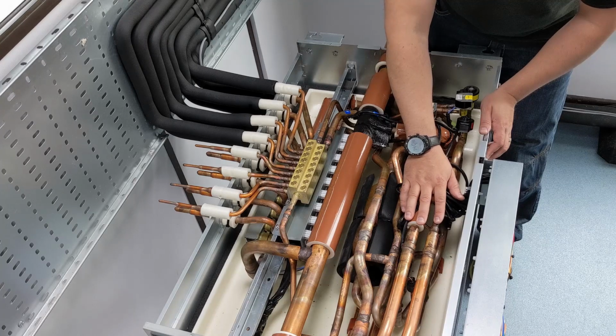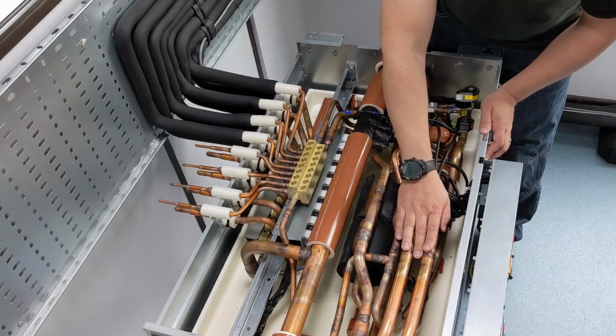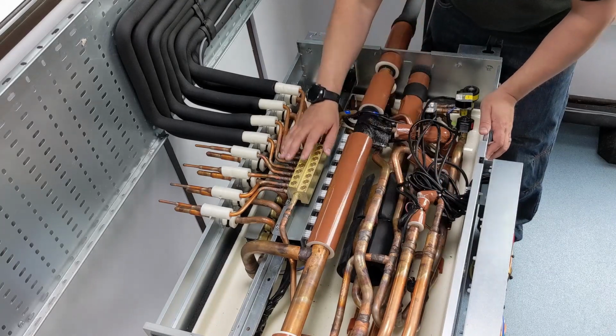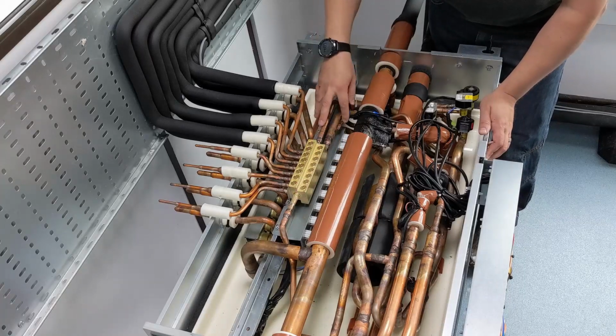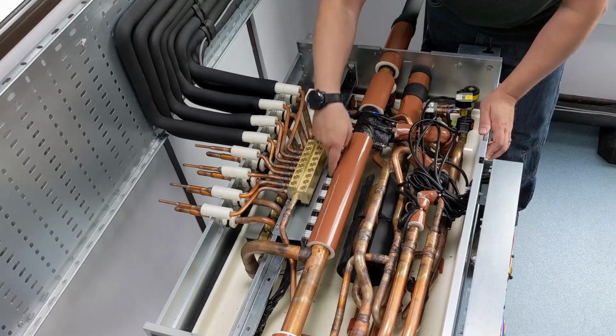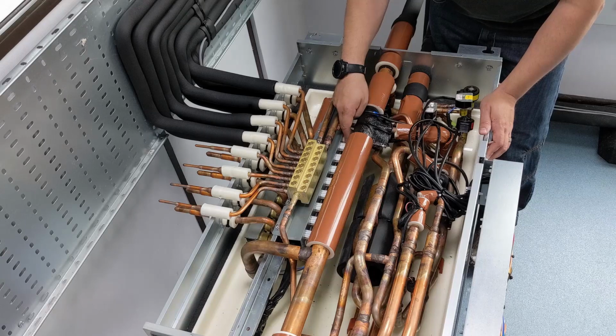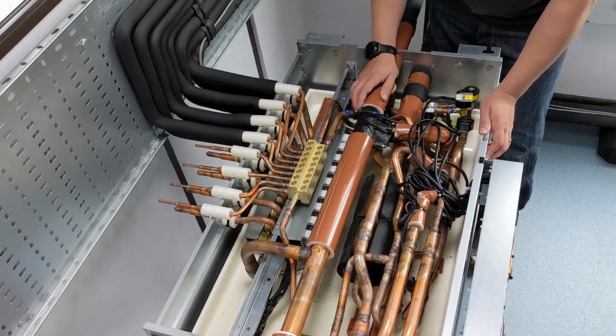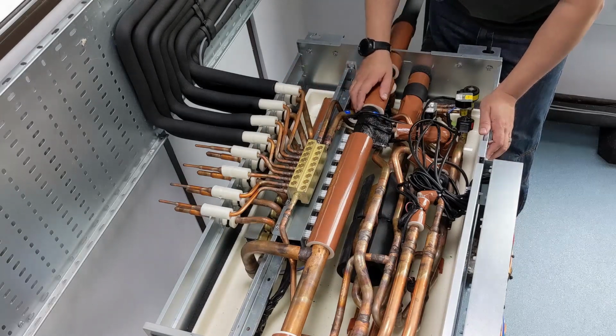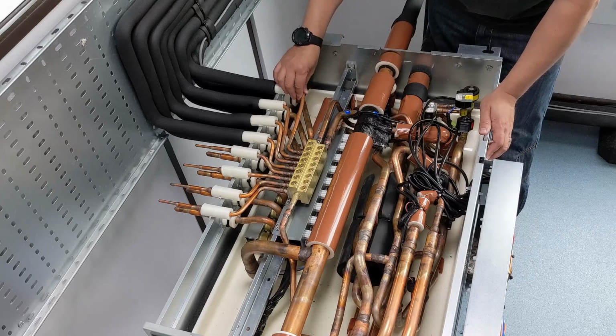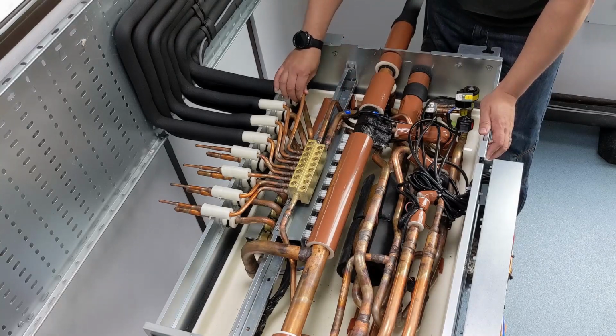We run the indoor units as flooded evaporators. That is until they're within 2 degrees of set point. So I've got my subcooled liquid refrigerant. I send that off to my control valves. So I've got a set of control valves down here. A and C on this side, which are going to be open when I'm doing cooling, and valve B on the other side, which is going to be shut because we're not doing any heating. I send that refrigerant off to the indoor unit. I say it goes through the expansion device.